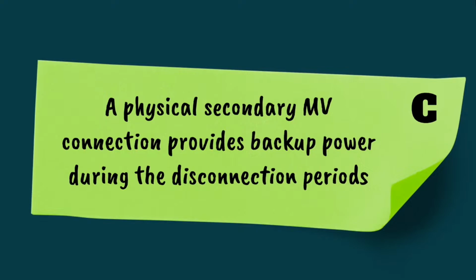This, of course, will make the restart of the whole wind farm much easier later on. It's not a critical item, but then again, if you are disconnected - the wind farm is disconnected for more than 5 days - most probably you will have to face at least one or two more days until you bring all your turbines up and running, simply because all the internal backup power has already been used, and the turbines themselves have gone into a cold shutdown.